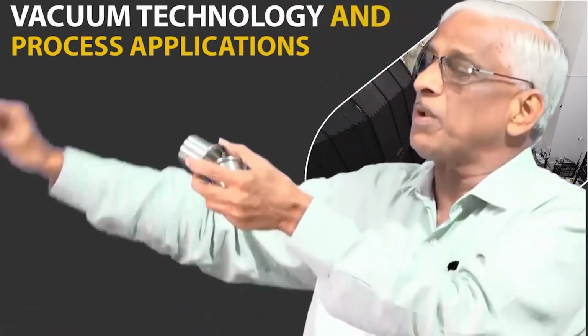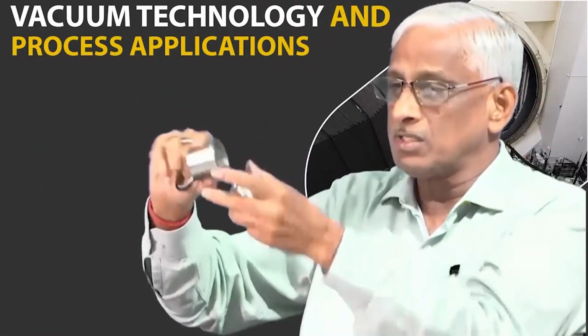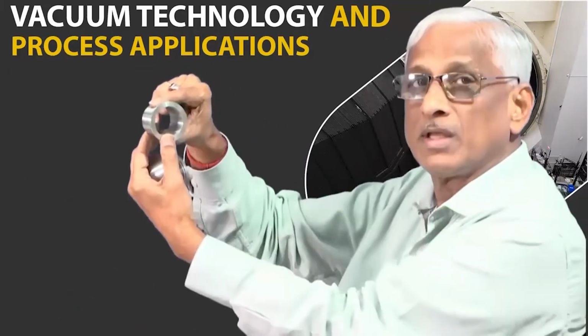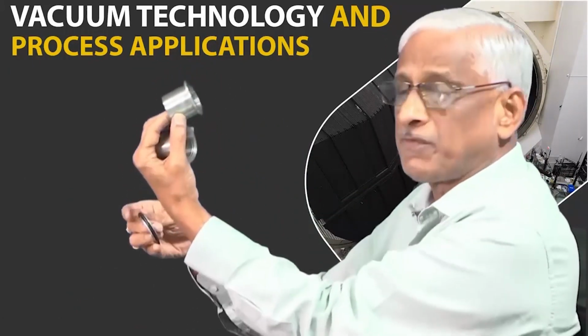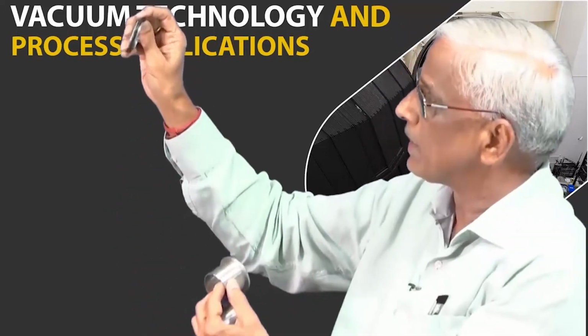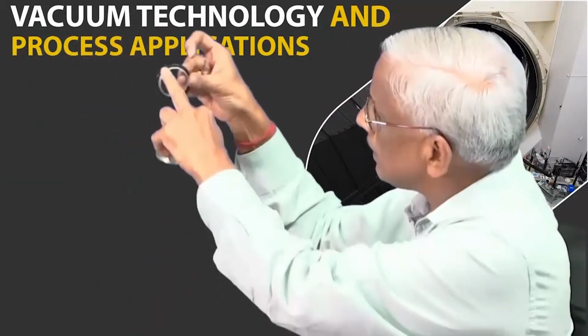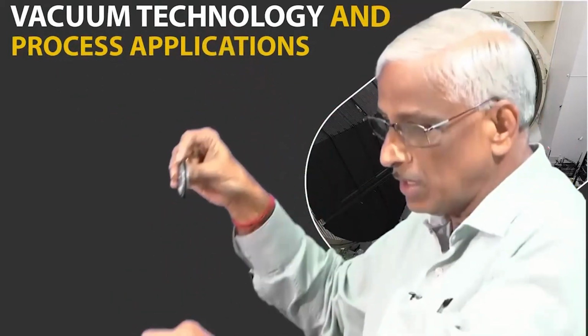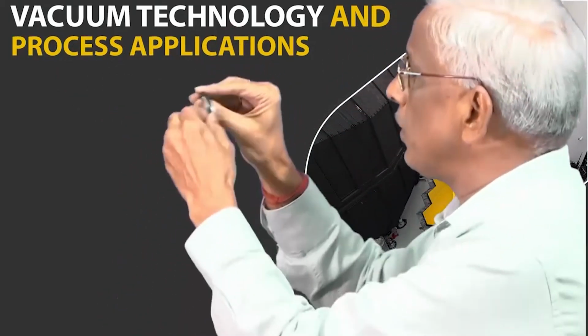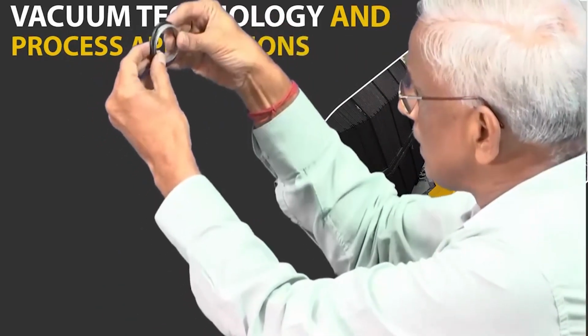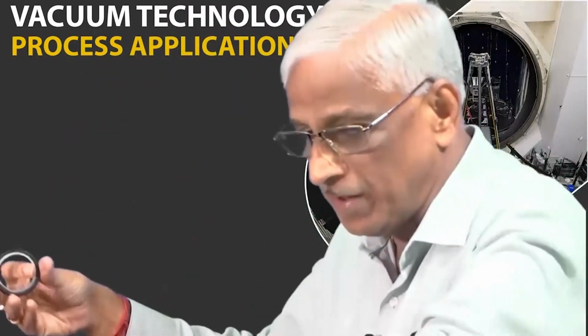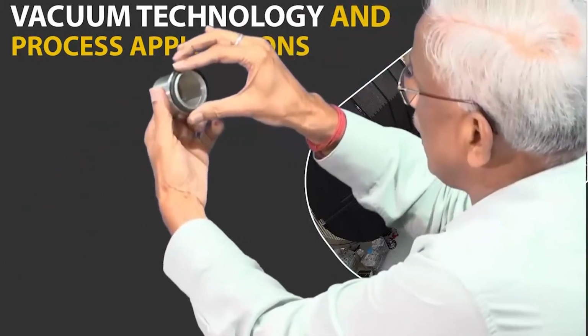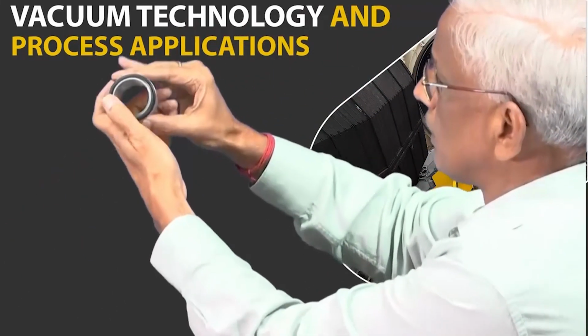And typical couplings that we see in day to day life for connecting pipes, the actual plumbing work gets soldered to this. This is my flange coupling type thing, KF coupling. This is a routine minus 5 to minus 6 torr, and this is my center ring and O-ring. The center ring is aluminum, and this is my O-ring. So, you can center it.